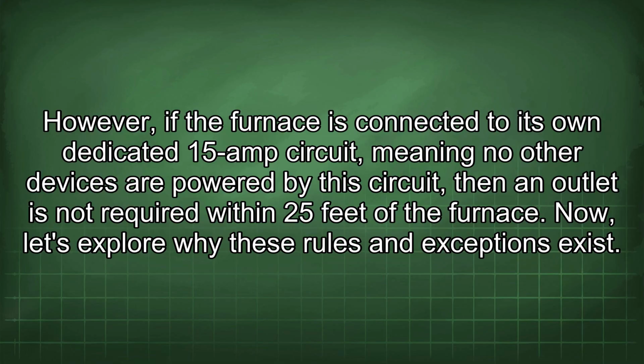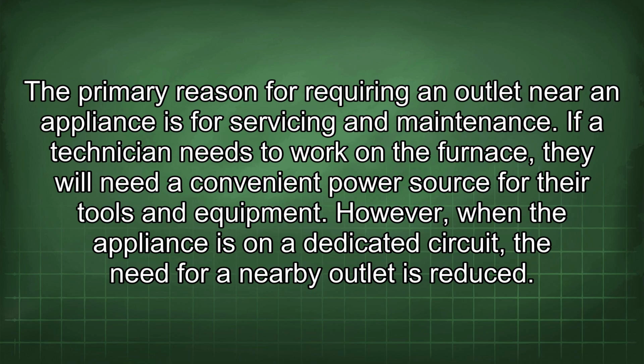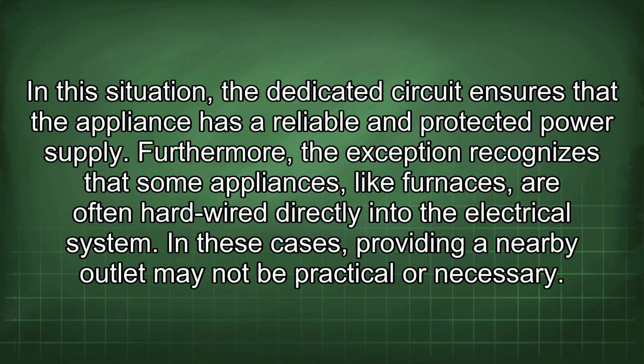Now, let's explore why these rules and exceptions exist. The primary reason for requiring an outlet near an appliance is for servicing and maintenance. If a technician needs to work on the furnace, they will need a convenient power source for their tools and equipment. However, when the appliance is on a dedicated circuit, the need for a nearby outlet is reduced. In this situation, the dedicated circuit ensures that the appliance has a reliable and protected power supply. Furthermore, the exception recognizes that some appliances, like furnaces, are often hardwired directly into the electrical system. In these cases, providing a nearby outlet may not be practical or necessary.